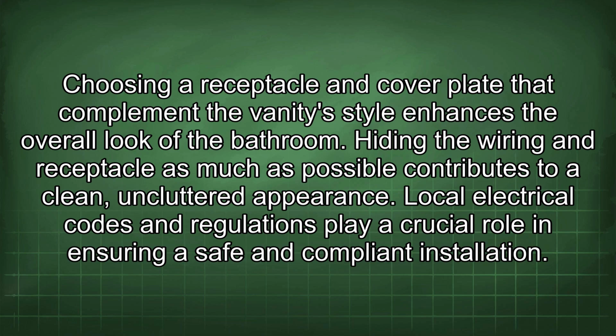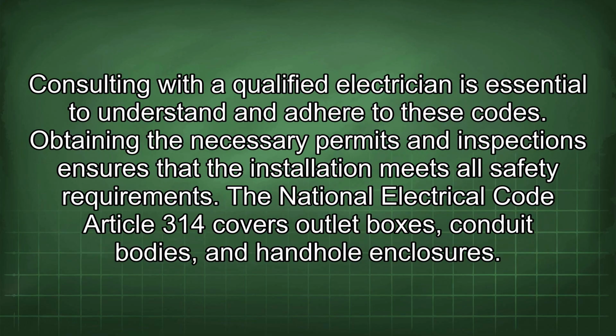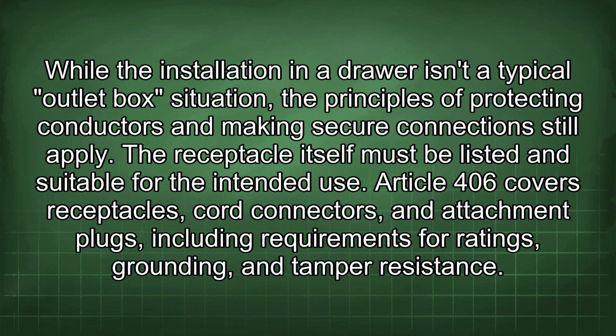Local electrical codes and regulations play a crucial role in ensuring a safe and compliant installation. Consulting with a qualified electrician is essential to understand and adhere to these codes. Obtaining the necessary permits and inspections ensures that the installation meets all safety requirements. The National Electrical Code Article 314 covers outlet boxes, conduit bodies, and handhole enclosures. While the installation in a drawer isn't a typical outlet box situation, the principles of protecting conductors and making secure connections still apply. The receptacle itself must be listed and suitable for the intended use.